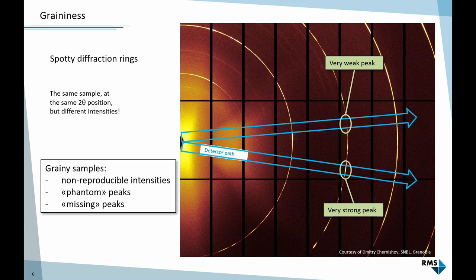What we get from a grainy sample is non-reproducible intensities. Sometimes peaks are much higher than we'd expect from our structure model, then we think is there some substitution happening? Sometimes peaks are much weaker or even missing. It will cause the same problem for refinement. It's not what we would expect and will lead us to a wrong path when it's just poor sample preparation.